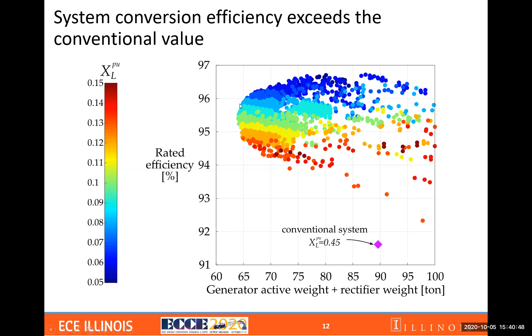So when we put everything together, we see the overall electromechanical conversion efficiency, and we compare it with a conventional system. You see that the net conversion efficiency of the conventional system is standing around 91.5%. With the integrated generator rectifier system, if we do it the same way, you can get close to 97%, which is a very impressive number. And even at the midpoint, you will enjoy an increase in conversion efficiency of around 4 to 4.5%.